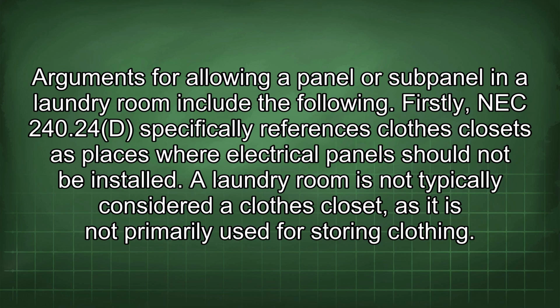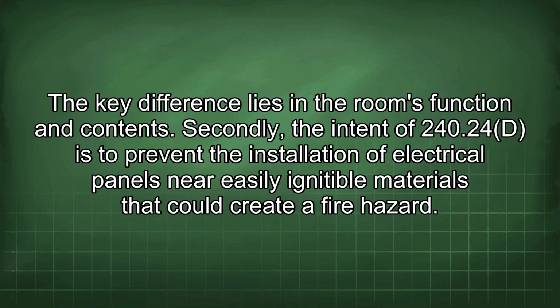Arguments for allowing a panel or subpanel in a laundry room include the following. Firstly, NEC 240.24(D) specifically references clothes closets as places where electrical panels should not be installed. A laundry room is not typically considered a clothes closet, as it is not primarily used for storing clothing. The key difference lies in the room's function and contents.